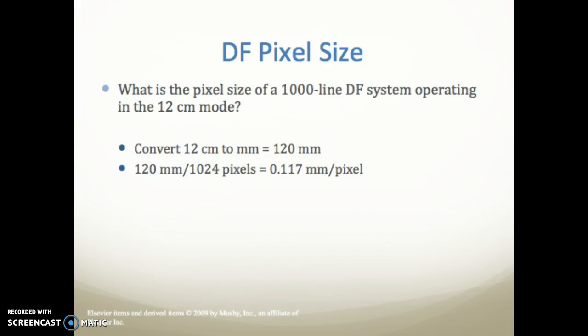Here's an example: what is the pixel size of a thousand-line DF system operating in the 12 cm mode? You convert 12 cm to millimeters, which is 120 mm, and divide 120 mm by 1024 pixels, giving you a 0.117 mm pixel.